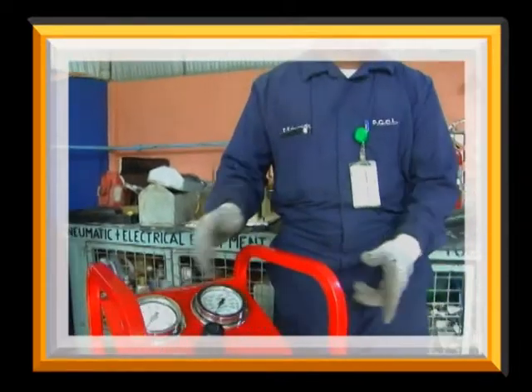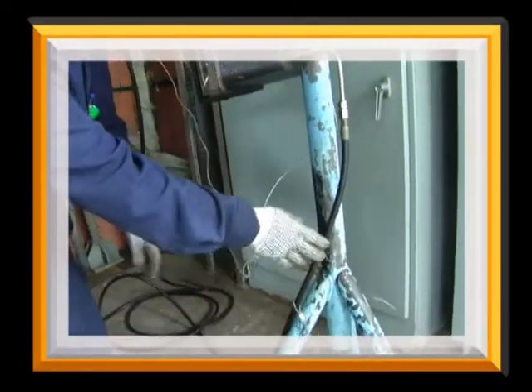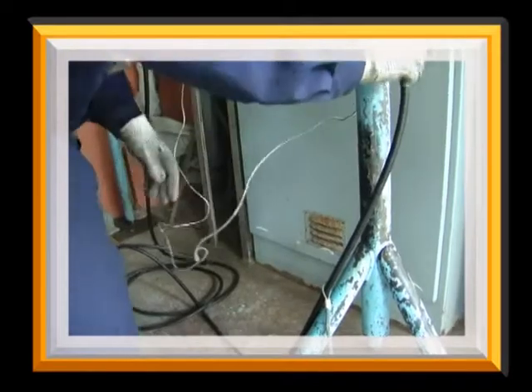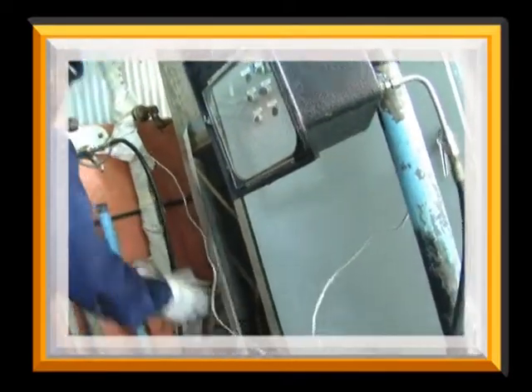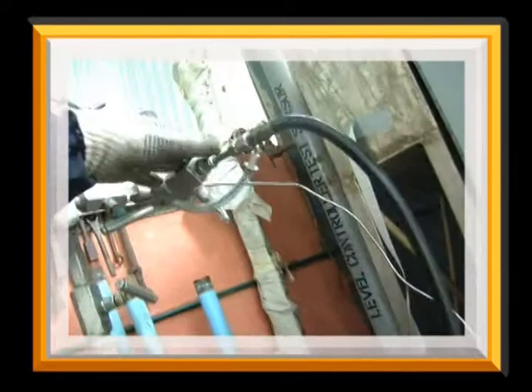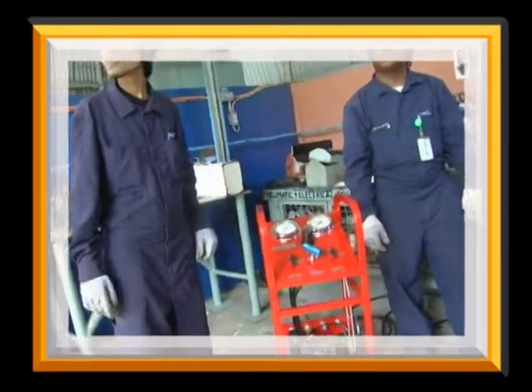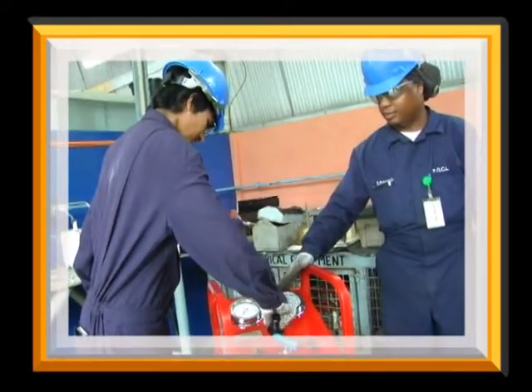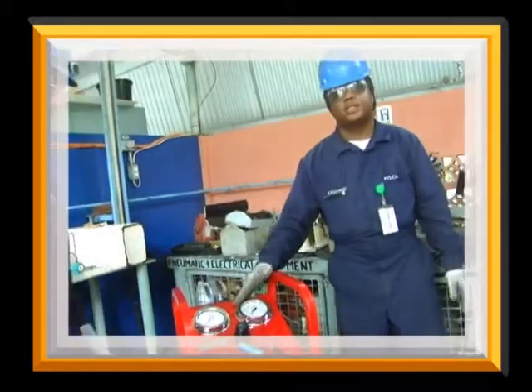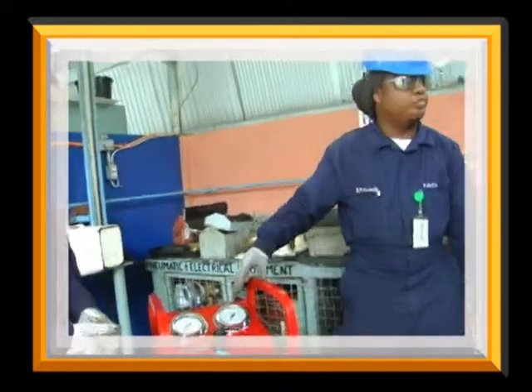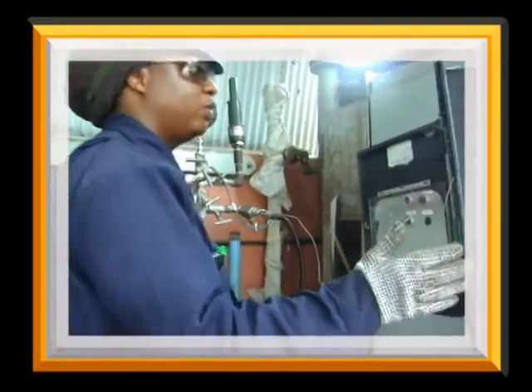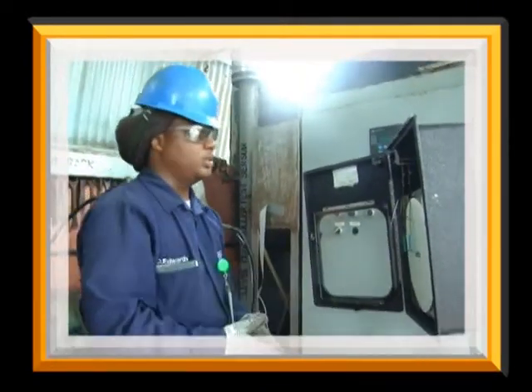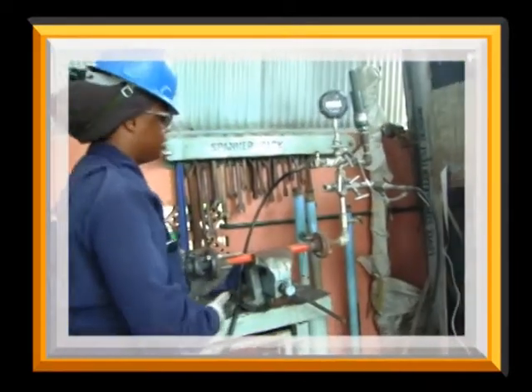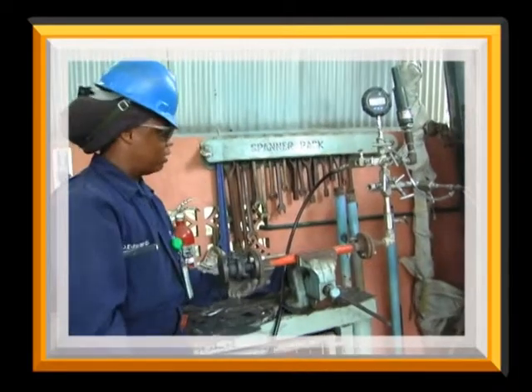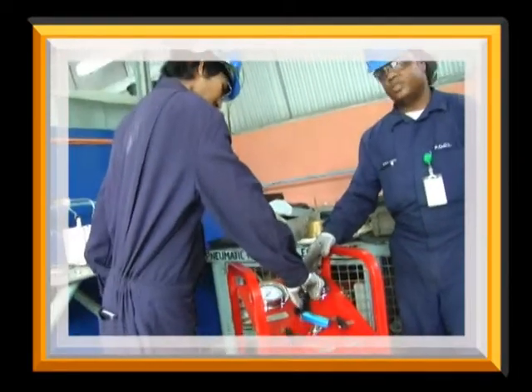The hydrostatic test kit and manifold should be properly secured to the pressure temperature recorder, since it should be used on all leak tests for ASME B31.3. As with any pressure test, the system is pressured slowly in stages. The pressure of the system is held and recorded at the various stages. When pressurizing any test system, continuous attendance and supervision is maintained at the test kit and the test gauge.